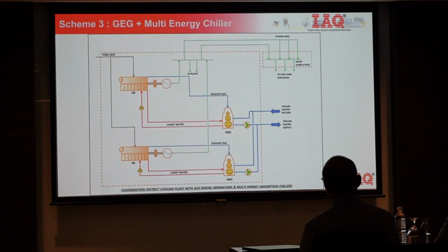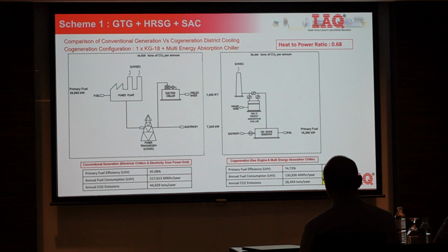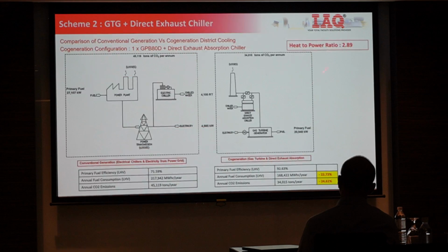Next is the gas engine with a multi-energy chiller. Same concept — the driver is a gas engine, extracting the jacket water and exhaust gas. The efficiency is 45% versus 74.72%. If you look at the heat-to-power ratio at the top, that's what determines what type of system you need. Heat to power here means the amount of chill water energy relative to the power ratio. You can see the chill water energy is much less than the power, so if your facility is power driven, this is the system to go for. If your facility is thermal energy driven, then a gas turbine may be a better option.